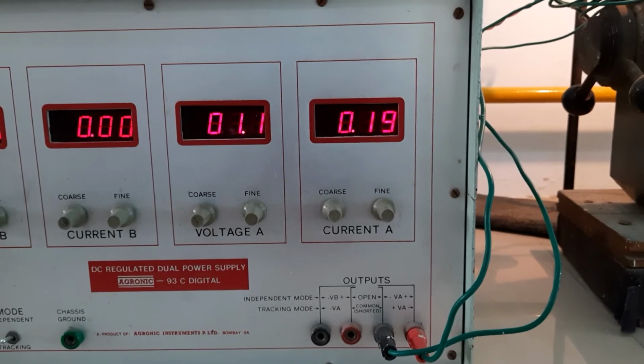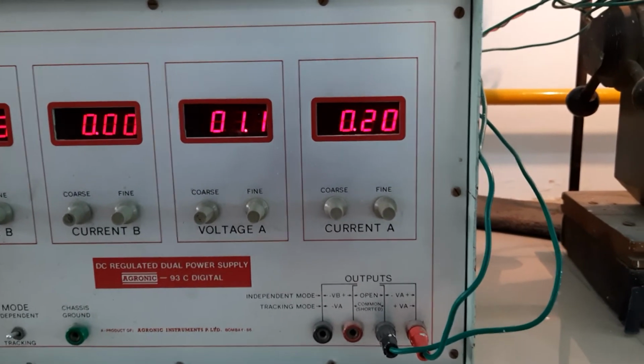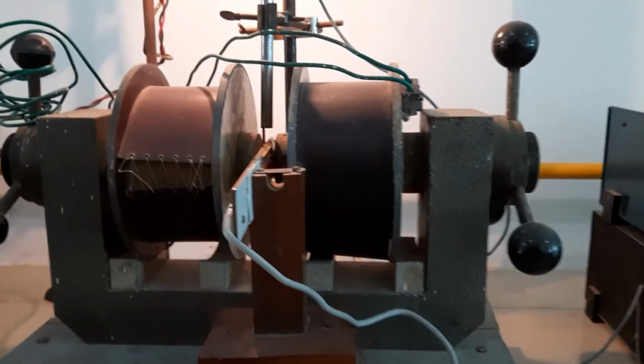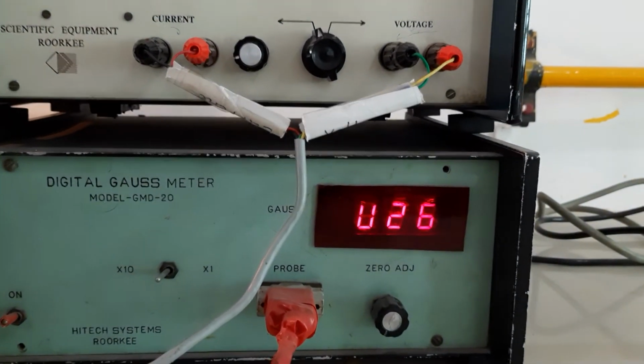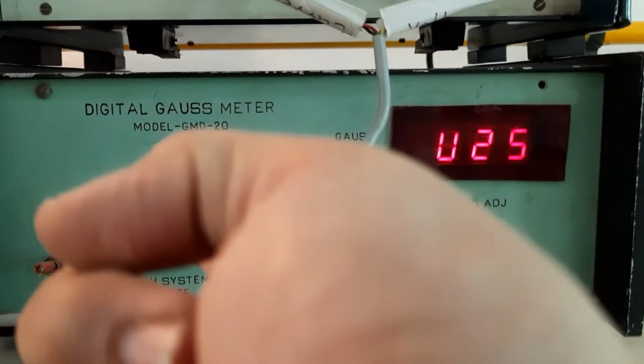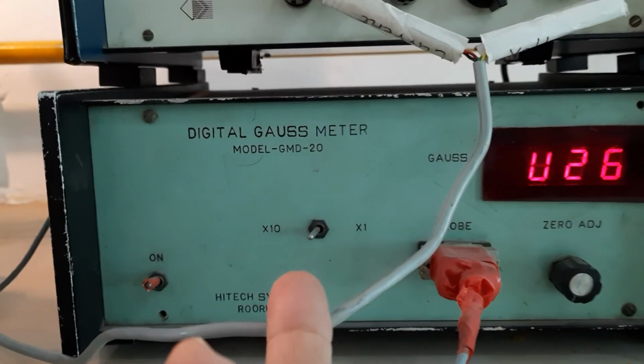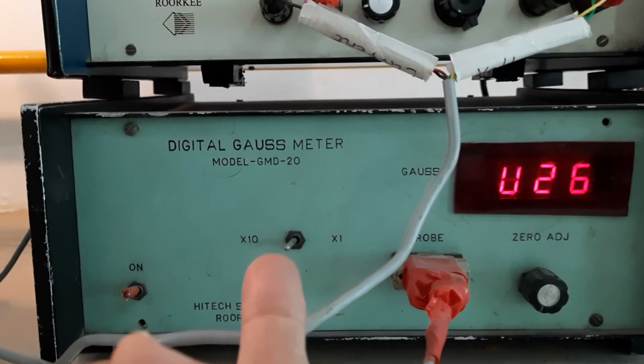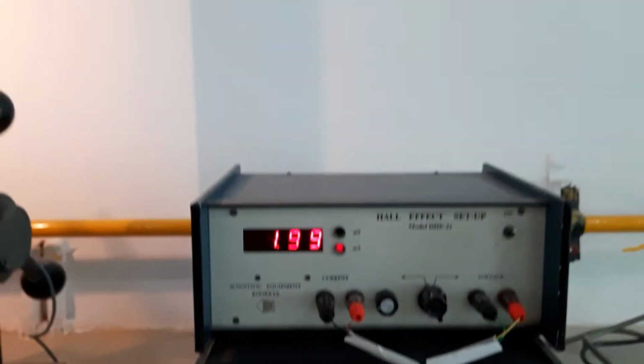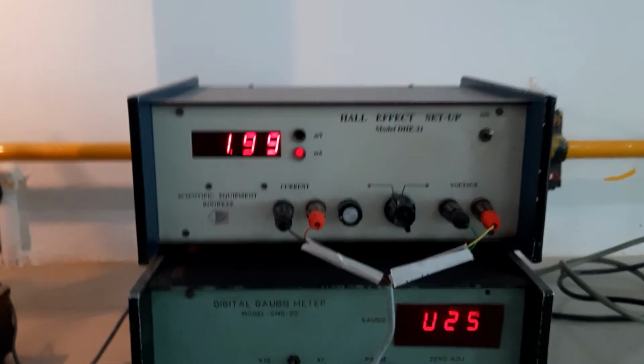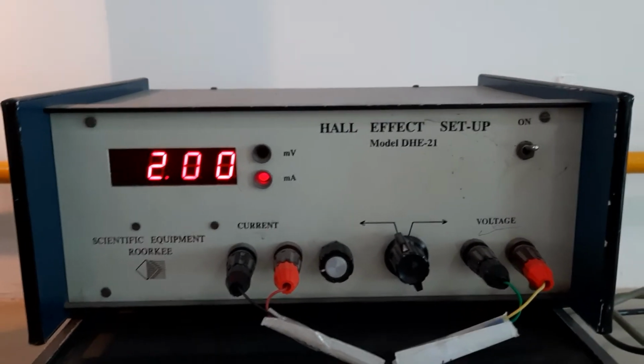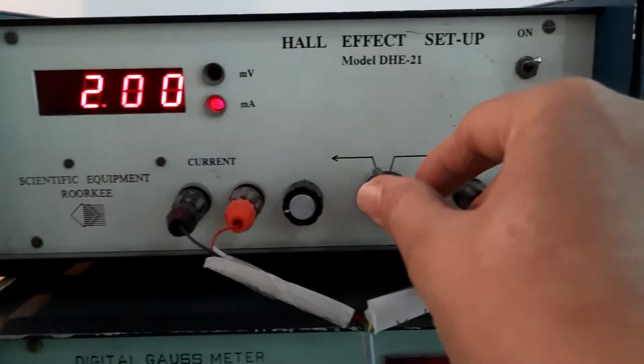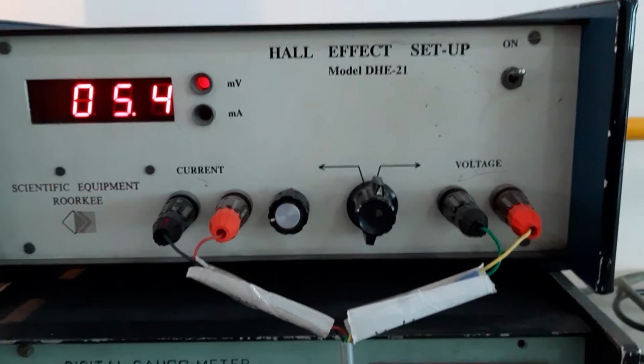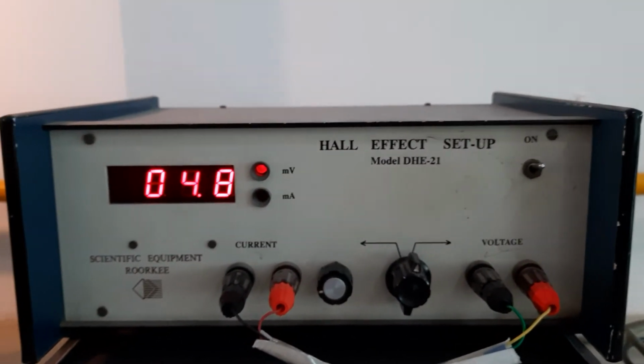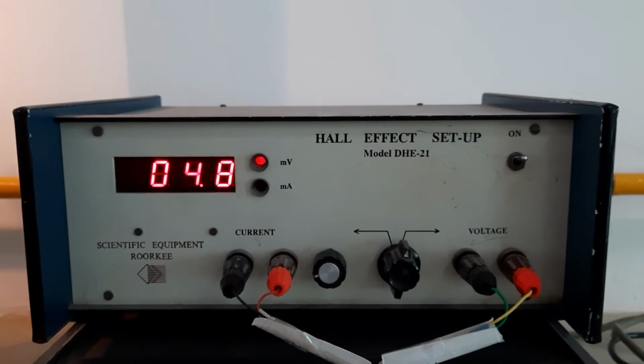Now when the current in this power supply is on 0.2, the magnetic field that it is creating between the two pole pieces of the electromagnet is 26 multiplied by 10. As you can see, there is a multiplier here of 10. So there is a field of 260 Gauss. Now at this particular field and the probe current of 2 milliampere, what is the voltage is what I have to measure. So I will switch this toggle switch in the voltage mode, and whatever voltage I get, I will allow it to steady and I will measure that voltage.